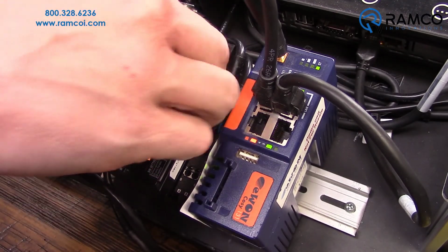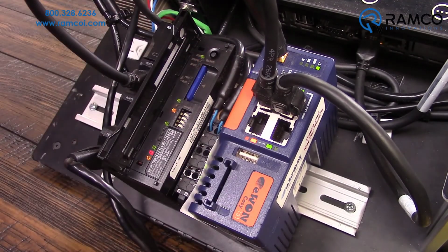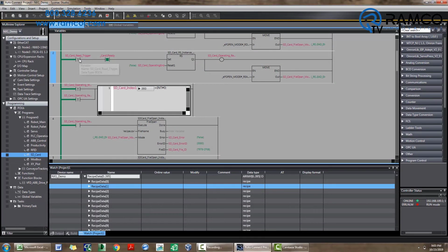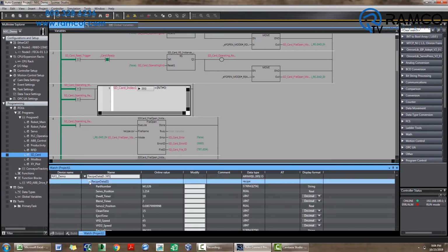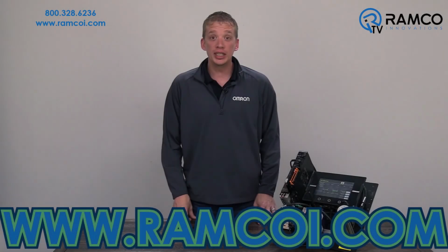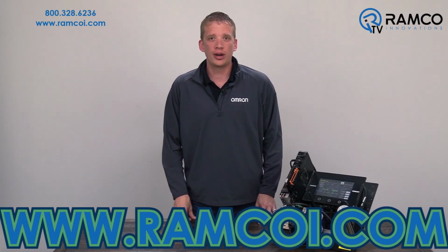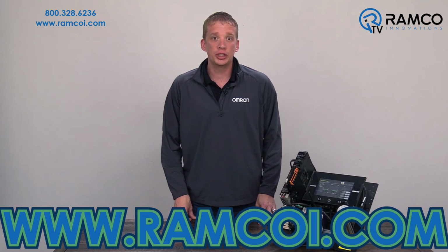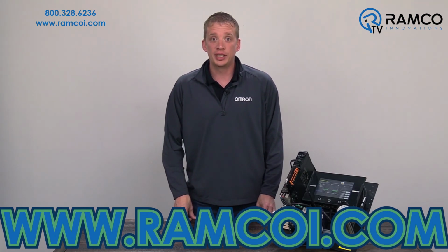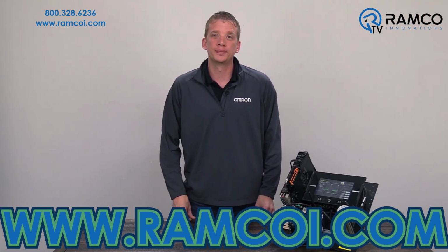Insert the SD card back in the processor. Go online, and when the SD card read trigger bit is toggled, it will automatically move the information from the SD card into your array. With the information in the array, you can now move these values into your timers, counters, and servo parameters. The ability to read information from the SD card allows you to easily make changes to your recipe files and provide secure backup of this information.